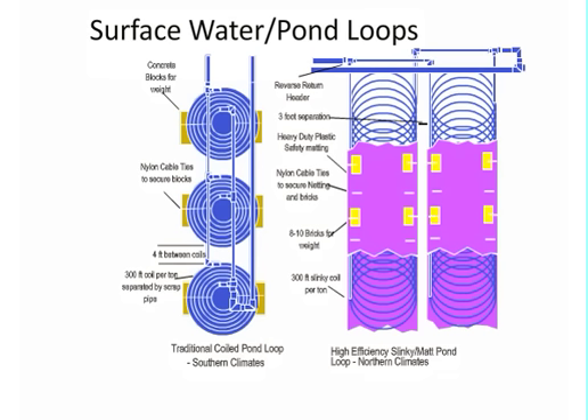I want to make sure you create some separation so you don't have abrasion, potentially from the expansion and contraction of the pipe due to thermal differences from season to season, and/or wave action or other movement down on the bottom. You don't want that sawing through the pipe over time.